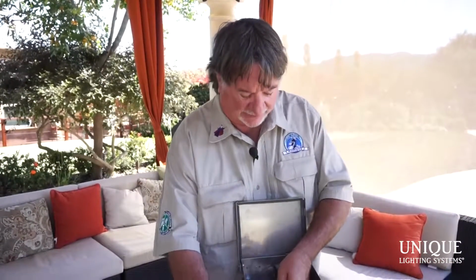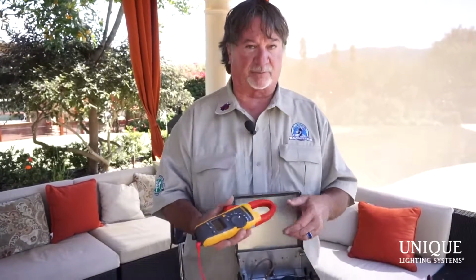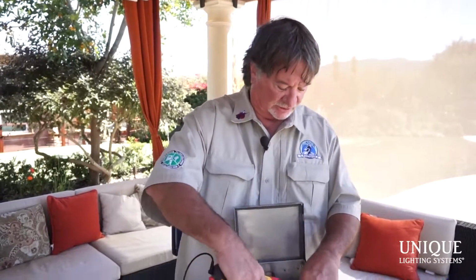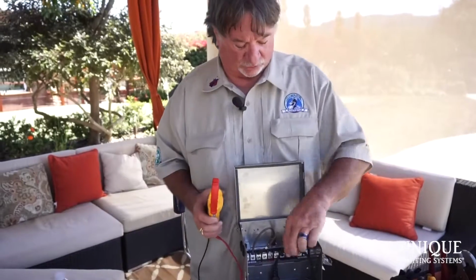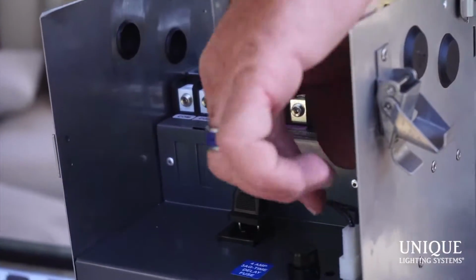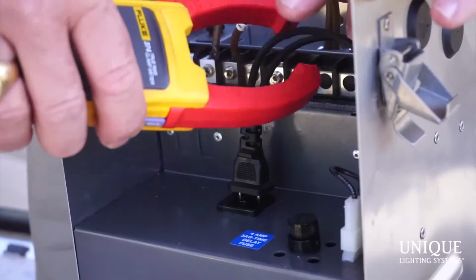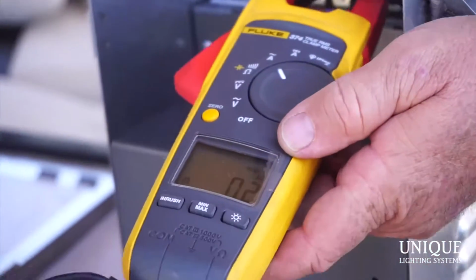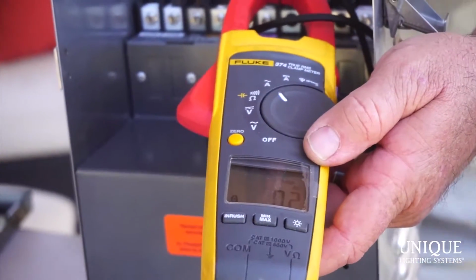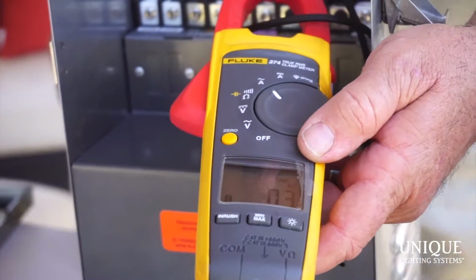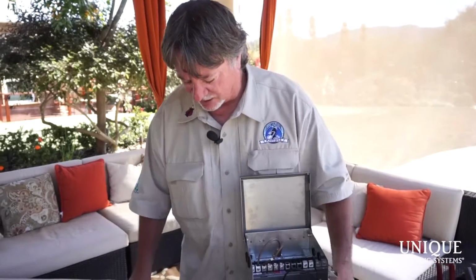Now the next thing I'm going to do is verify my primary volt amperage. We have a split wire, and also a little loop wire right here. So we do the same thing: take our amp probe, run it around that wire, and it says 0.3.